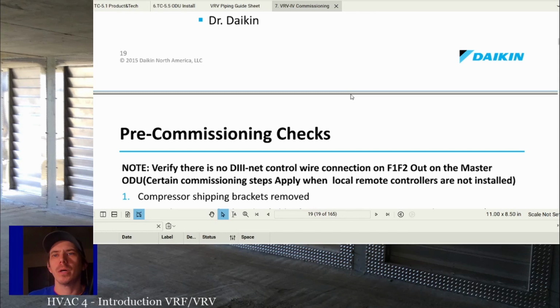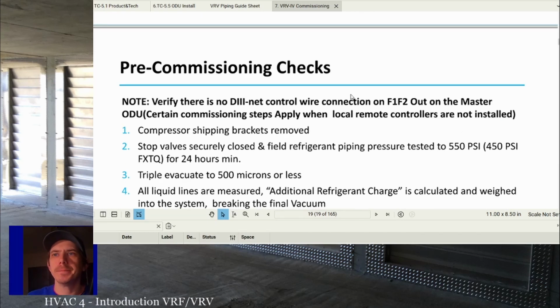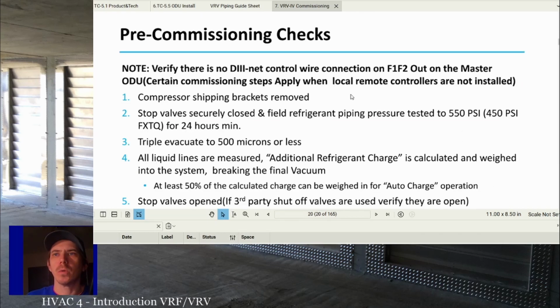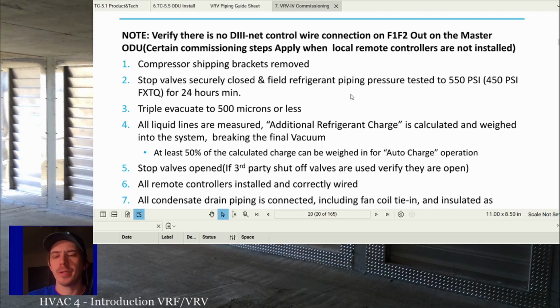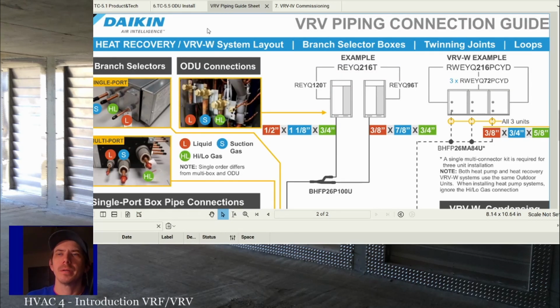All right, so this is actually a commissioning guide. So I want to discuss some of the important installation points that you have when doing VRF. Well, no, let's talk about piping and wiring first. Let's not make it complicated. Before we get into commissioning, here's a piping connection sheet for Daikin. All right, so let's talk about piping. Remember, you have liquid, suction, high-low gas. All right, liquid, suction, high-low gas.